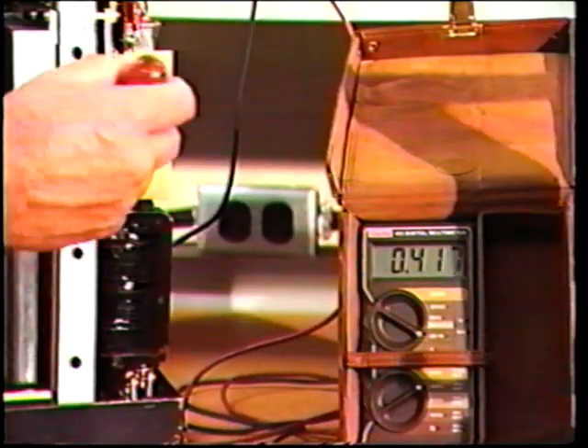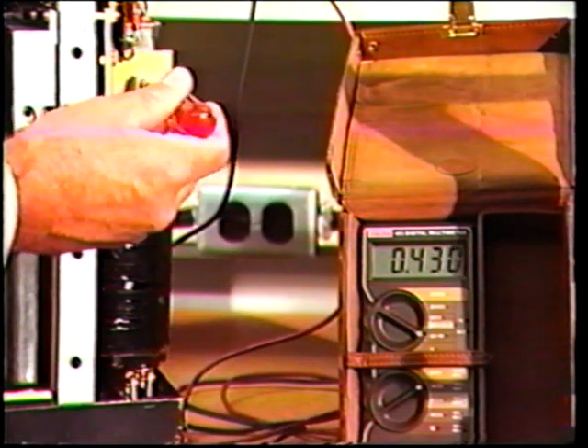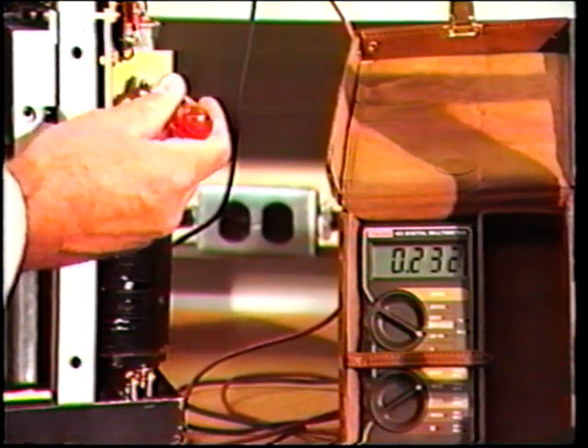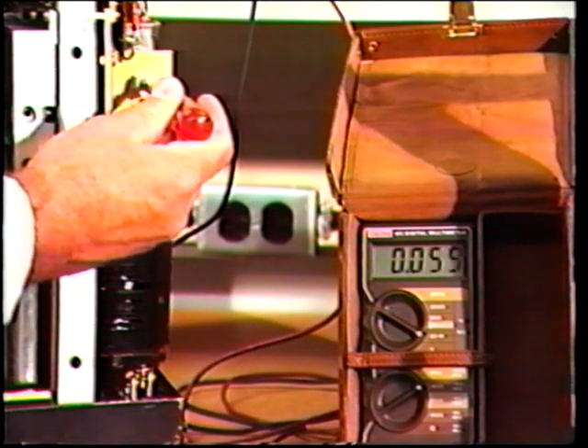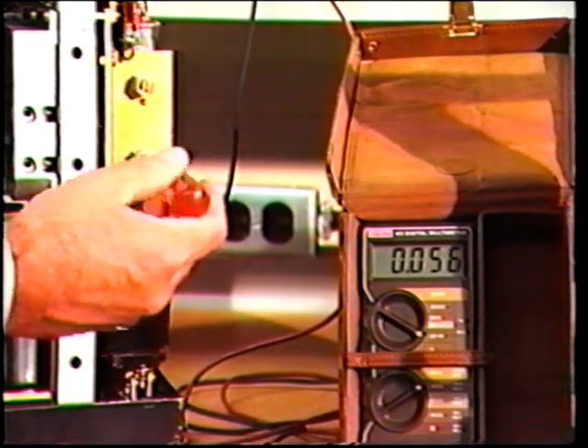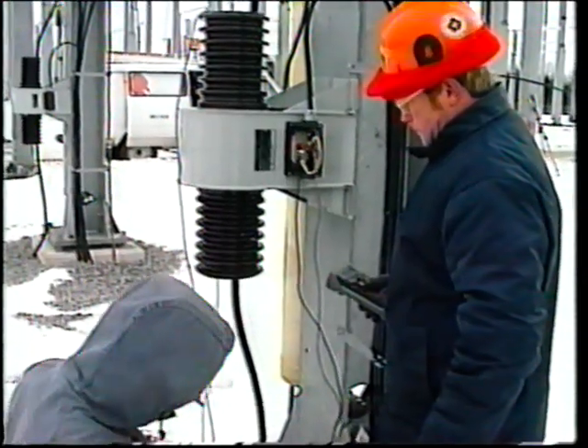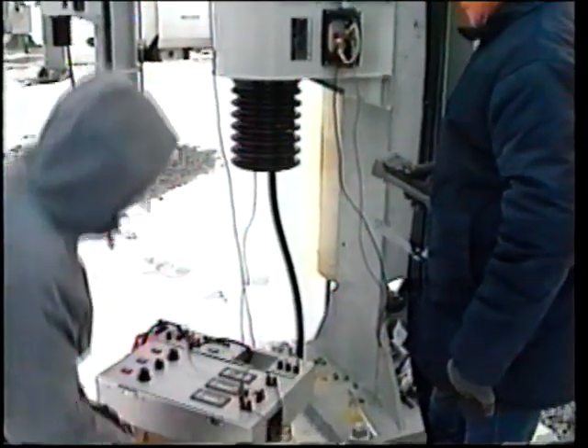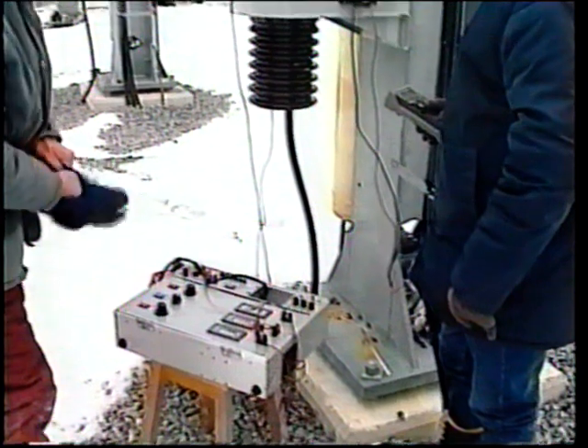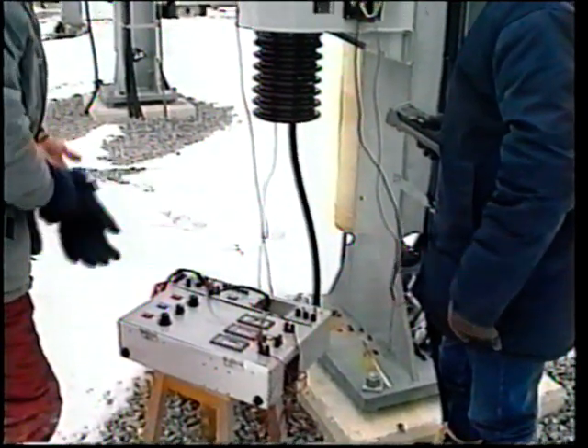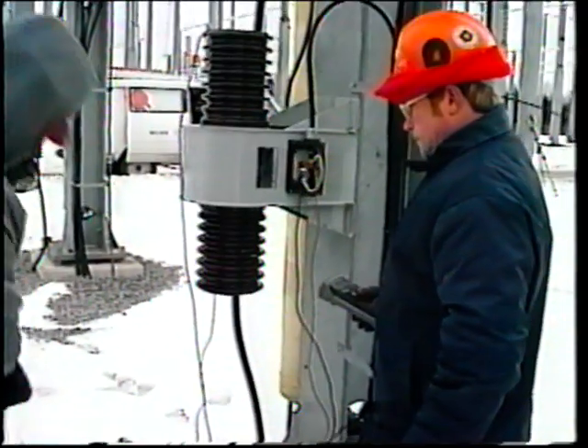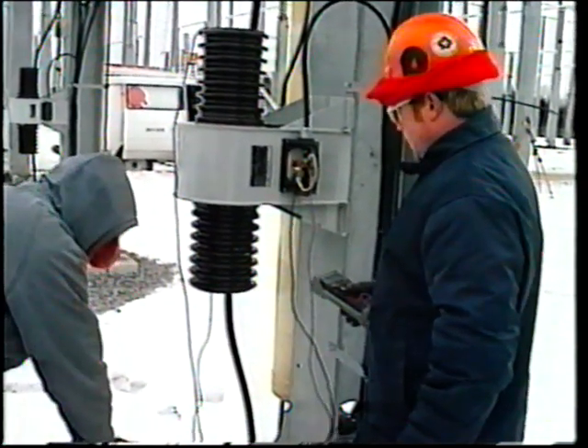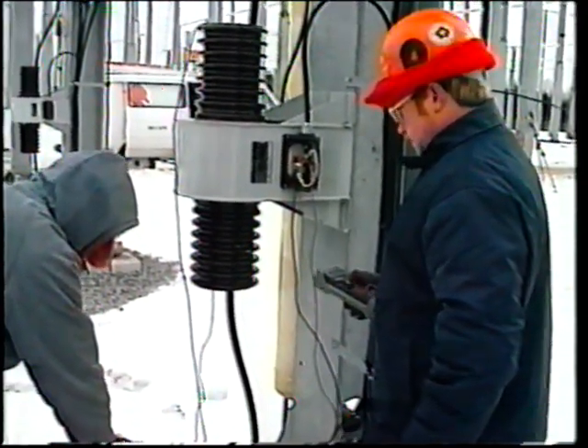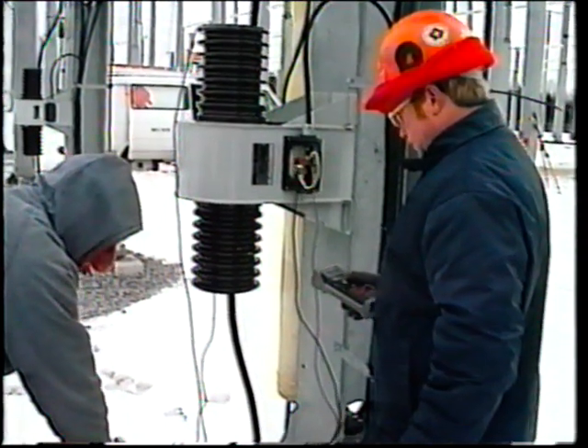First, the relays must be calibrated and set according to instructions. After calibration, the complete protection scheme must be checked for operation by simulating fault conditions. As we noted in earlier tapes, this is done by injecting controlled values of current into relay primary and secondary circuits. This will verify that the total scheme, from fault detection through to breaker tripping, is functioning correctly. All of this must be carried out before the new installation is energized.